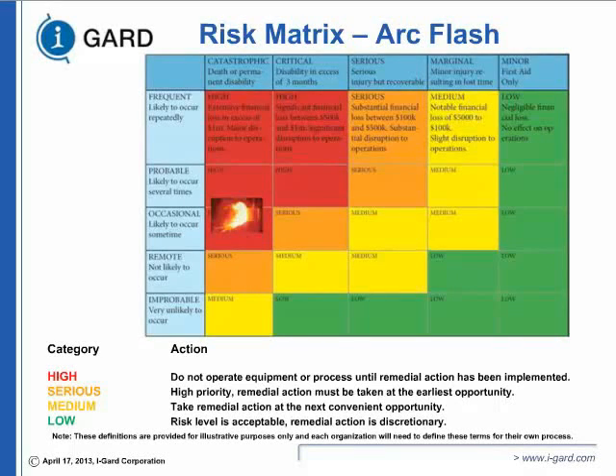So on, going to serious and medium, and when you go to low, the risk level is acceptable, remedial action is discretionary. That means you may have equipment loss due to flash, but you may not have people loss. All safety depends on the primary goal to protect people first, then you protect the equipment. Ideally, you want to protect both. Okay?